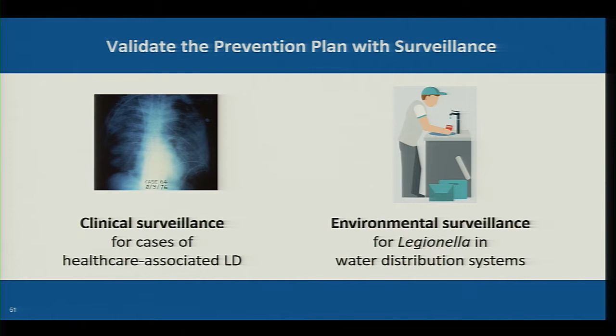The way we validate that HCA-LD prevention plans are working in the VA is to do surveillance: clinical surveillance for cases of HCA-LD and environmental surveillance for Legionella in water distribution systems. Each can indicate that implementation of controls to reduce Legionella risk may need to be adjusted. Let's look at each surveillance system a little closer.